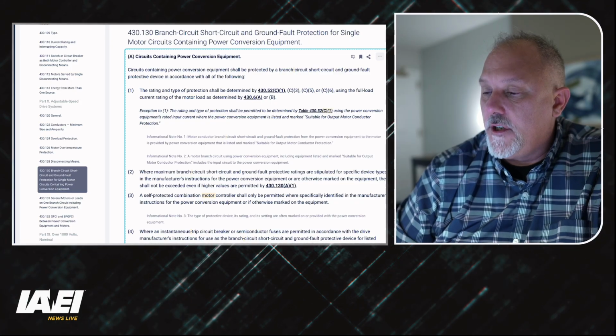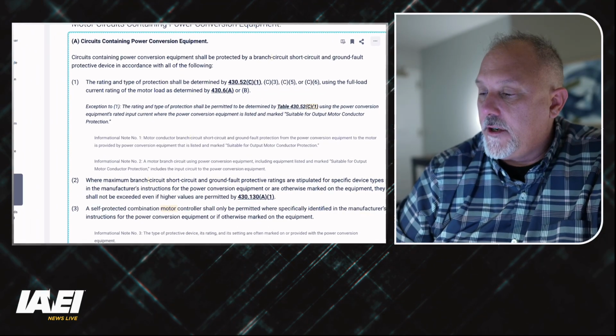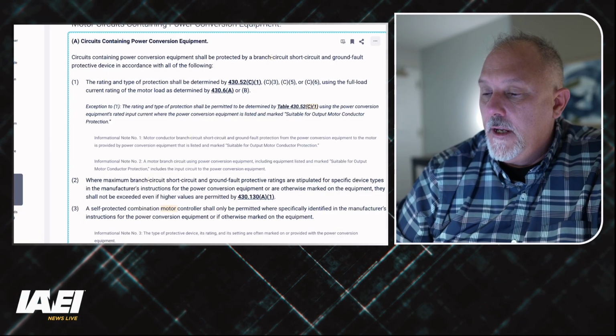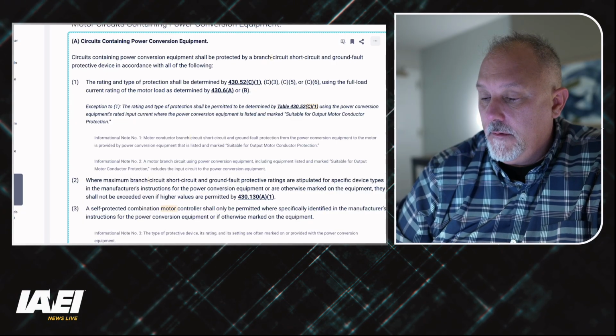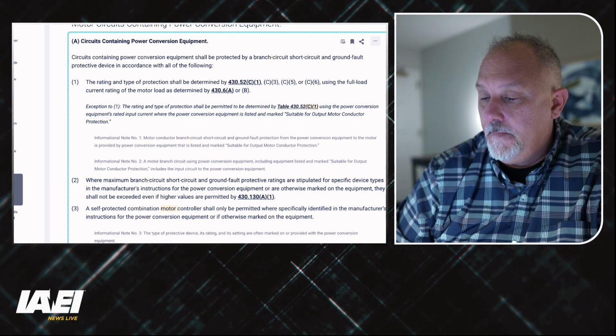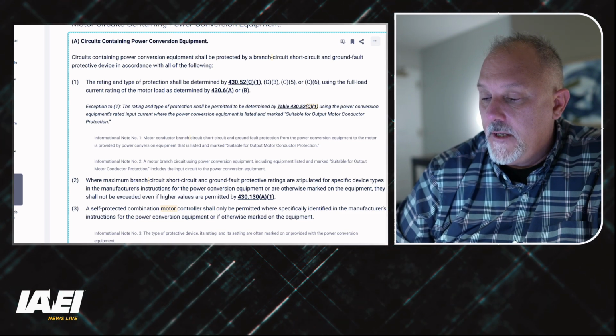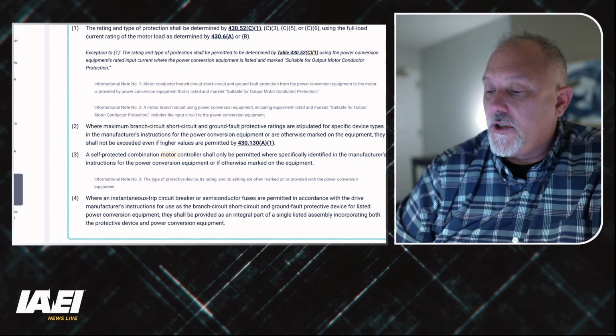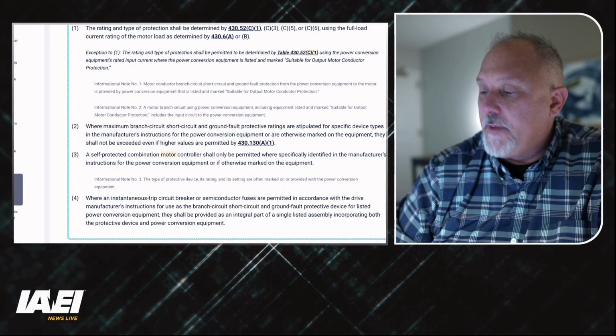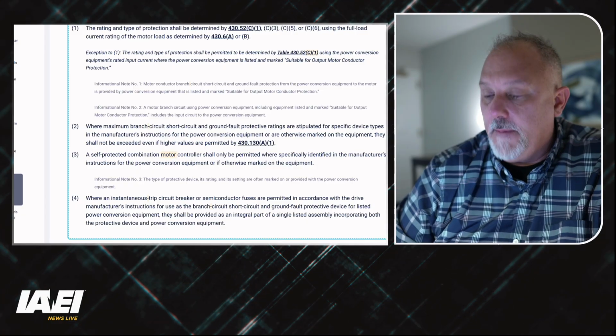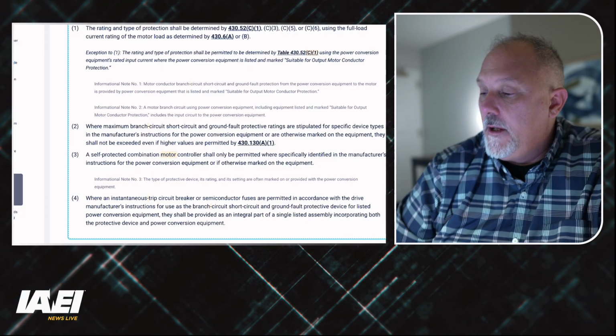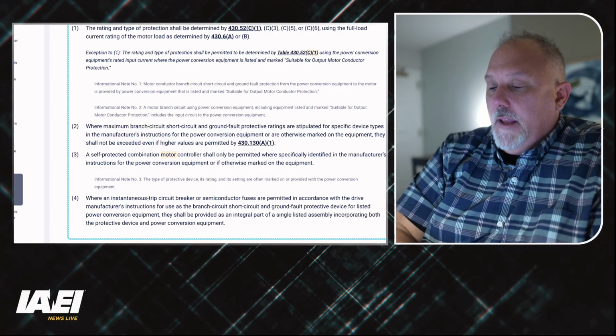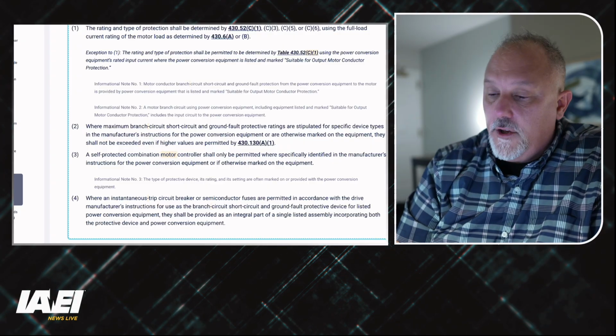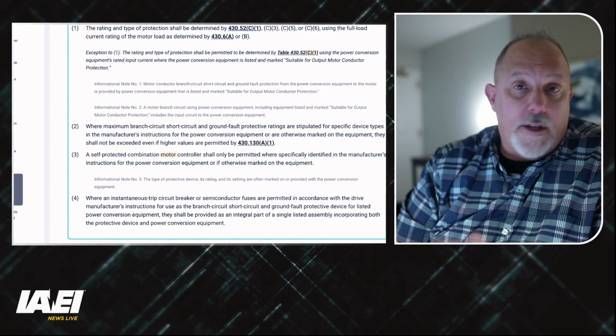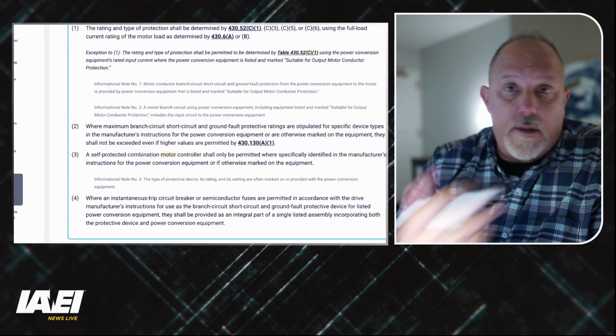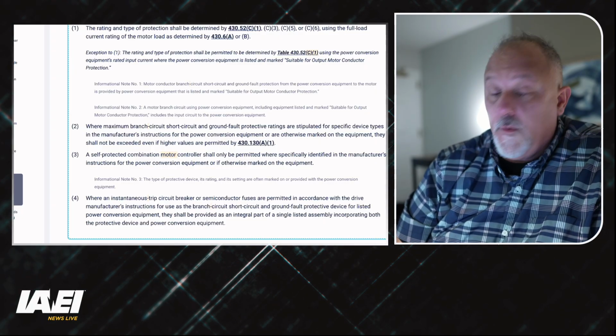Circuits containing power conversion equipment shall be protected by a branch circuit, short circuit, and ground fault protective device in accordance with all of the following. Manufacturer's maximum branch circuit, short circuit, and ground fault protection ratings are stipulated for specific device types in the manufacturer's instructions for the power conversion equipment. They shall not be exceeded even if higher. So that's telling you, this item 2 is telling you, look, some of these drives will tell you what the maximum needs to be, what your protection needs to be.